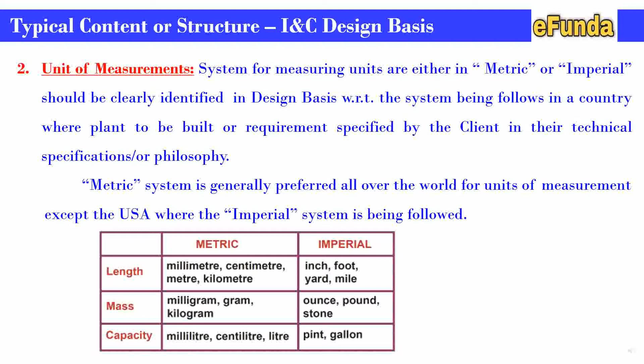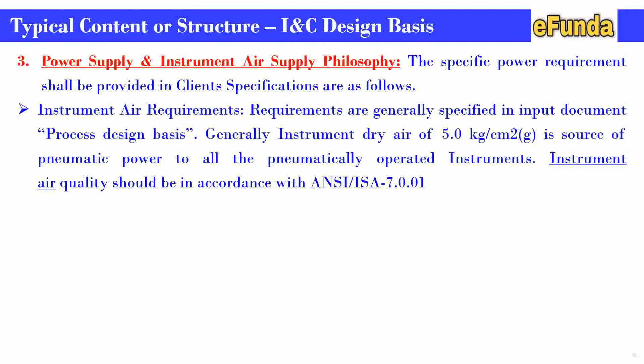Power supply and instrument air supply philosophy. The specific power requirement shall be provided in the client specifications as follows. Instrument air requirements are generally specified in the input document, that is the process design basis. Generally, instrument dry air of 5 kg per centimeter square is the source of pneumatic power to all pneumatically operated instruments. Instrument air quality should be in accordance with ISA 7.0.01. One can see in the below table where the instrument air data and operating conditions as well as the design conditions are specified. Minimum, normal and maximum conditions are given.